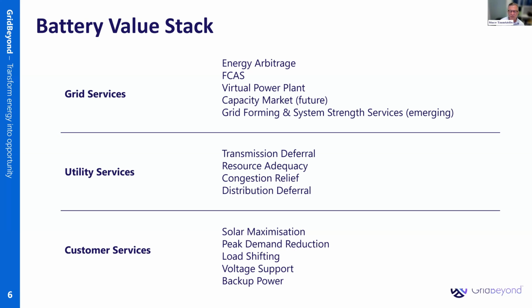Now, the value of those won't be translated on the energy bill every month, but where they are translated is the loss of production time. So if you've got a voltage sag and it turns off your premises, and then you have to restart your machines, and that's cost you $20,000 worth of lost revenue, that's the value that a battery may bring. So if you've got a problematic site where there's voltage sags, swells, harmonics, after you've gone to James and he's fixed all his problems with harmonic filters and power factor correction, and that problem persists because it's coming from the network, then a battery may be the option.